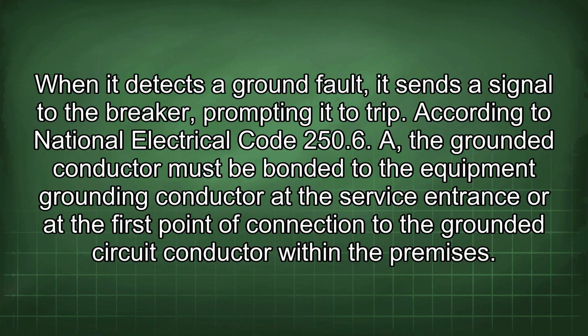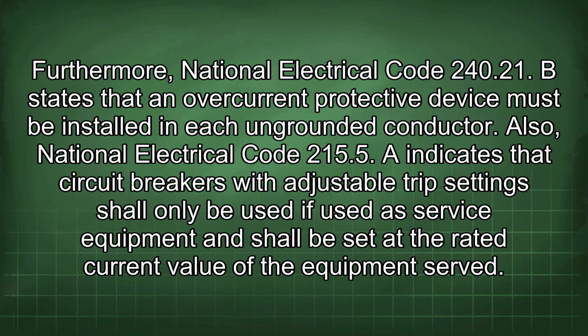According to National Electrical Code 250.6(A), the grounded conductor must be bonded to the equipment grounding conductor at the service entrance or at the first point of connection to the grounded circuit conductor within the premises. Furthermore, National Electrical Code 240.21(B) states that an overcurrent protective device must be installed in each ungrounded conductor. Also, National Electrical Code 215.5(A) indicates that circuit breakers with adjustable trip settings shall only be used if used as service equipment and shall be set at the rated current value of the equipment served.